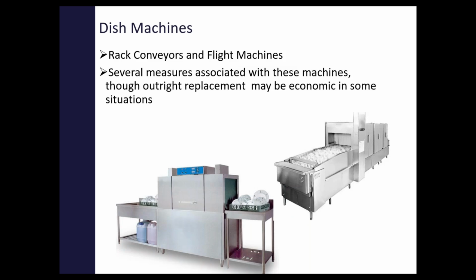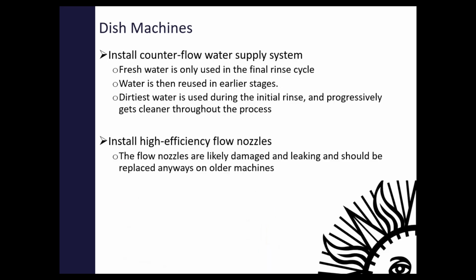Usually, if it's not an Energy Star rated machine, full replacement might pay back, just depending on how often that kitchen is used. Another thing you can do is just reconfigure the water supply so that it's a counterflow water supply, so that you're always using the cleanest water at the final rinse, and then you move that water through the next basin, provide the second rinse, and then you move that water, that very dirty water now, to provide the first rinse and take off the bulk of the grime and such from the flatware and plates.